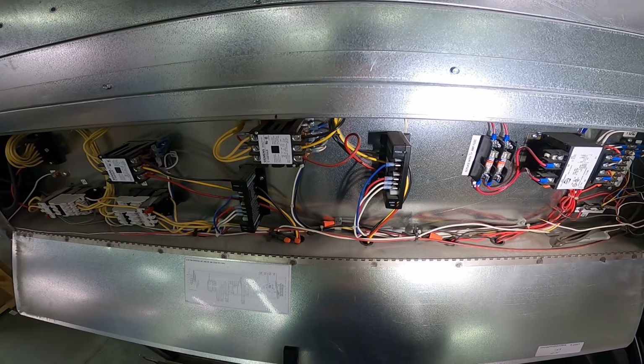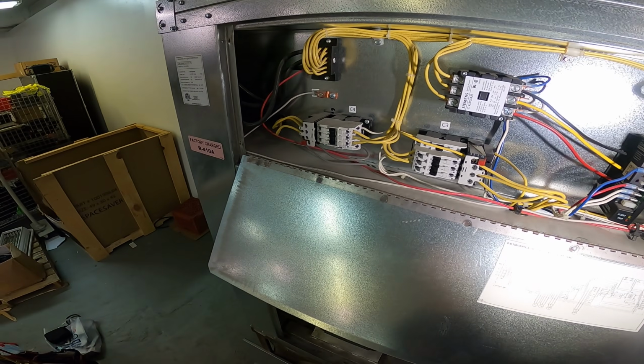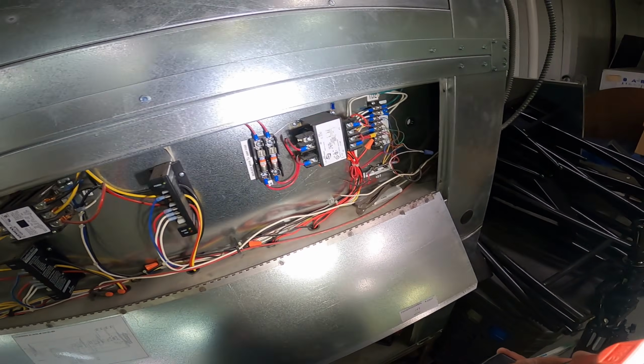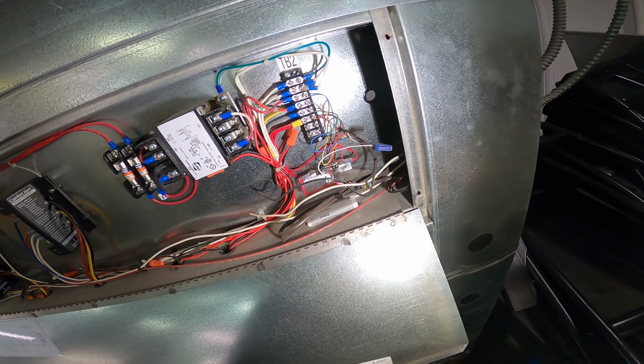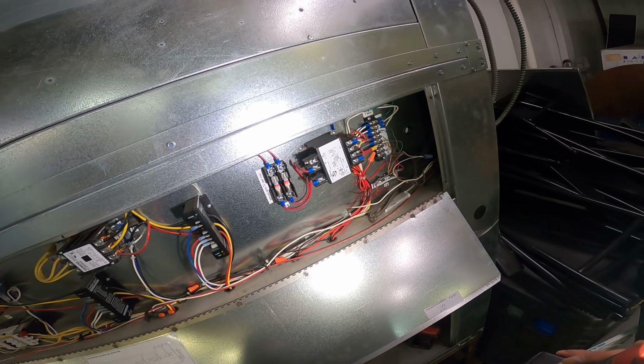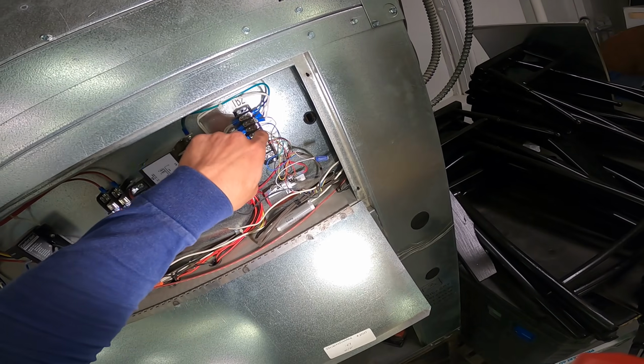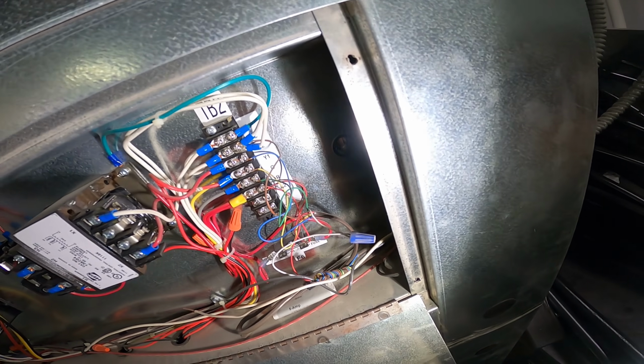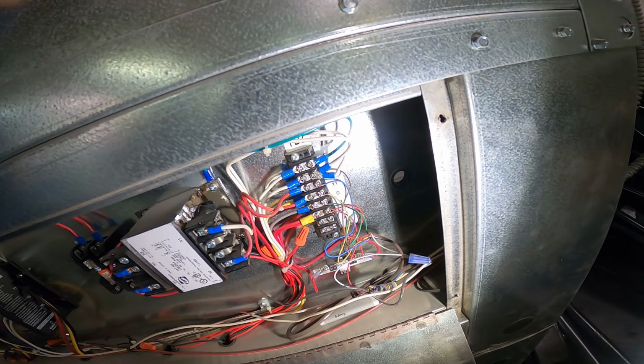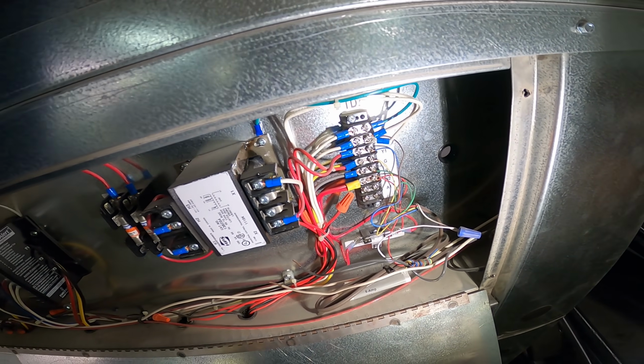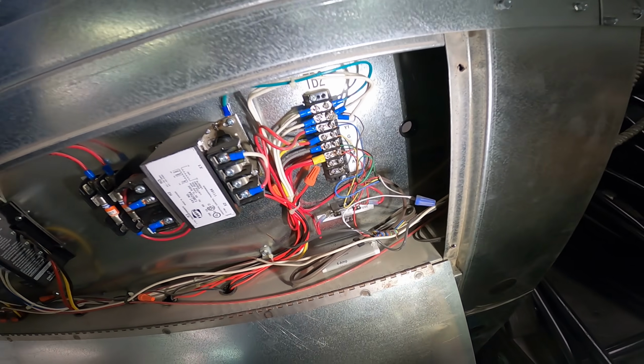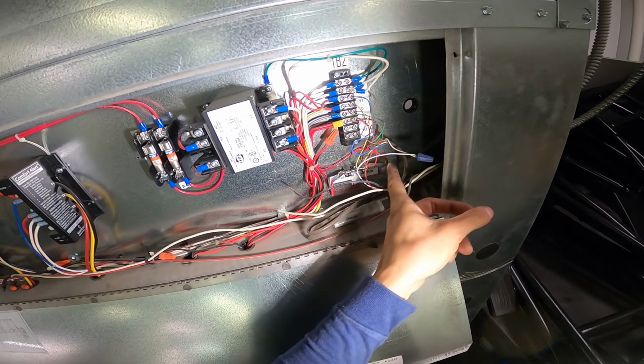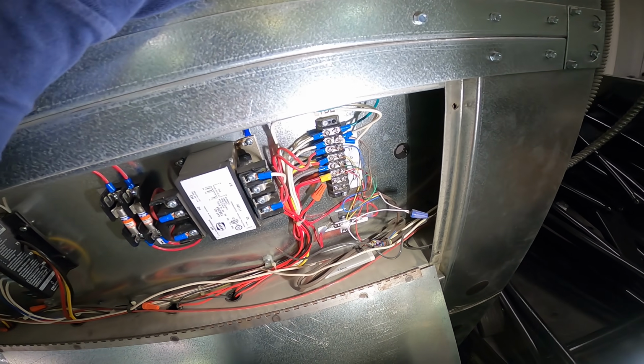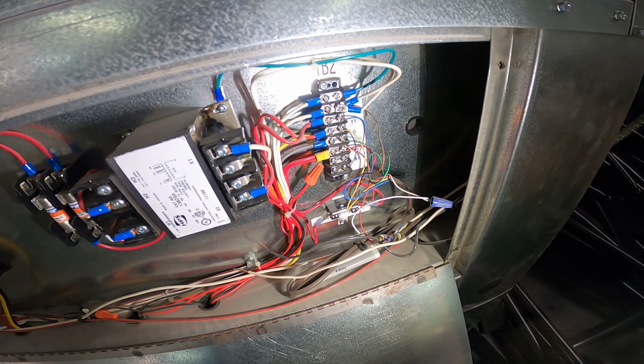Let's go over some of the controls. All right, here is our control panel. And for the most part, everything is mechanical as far as controls here. So let's see what's going on. Right here, we have a terminal block. As you can see, it's labeled with things such as C, Y1, Y2, G. So we know that's our terminal block for our thermostat. These little wires coming in, that's our thermostat wiring, and that comes, of course, from the thermostat.